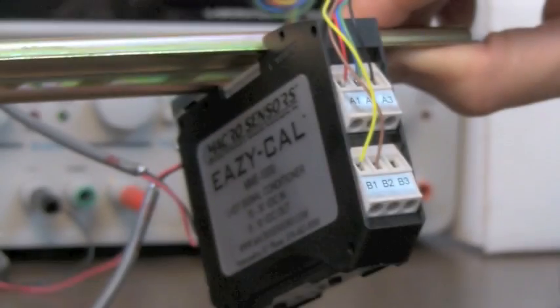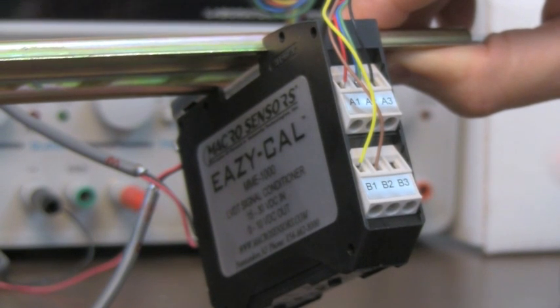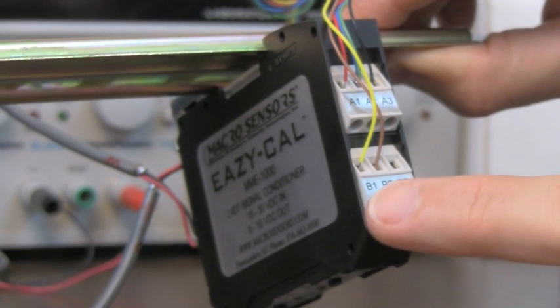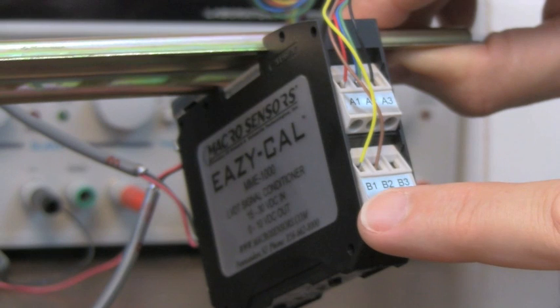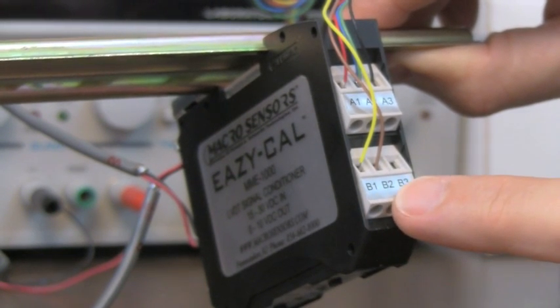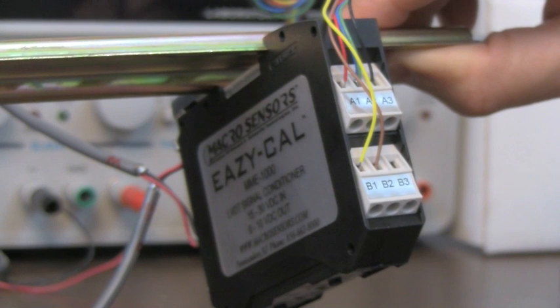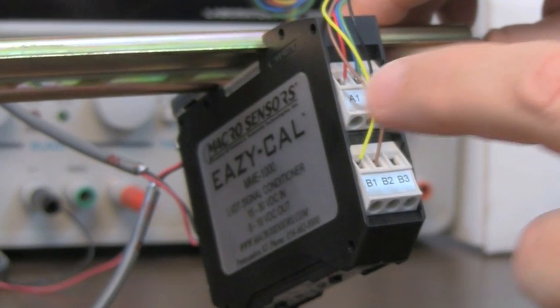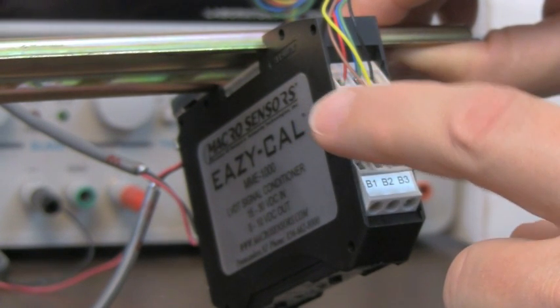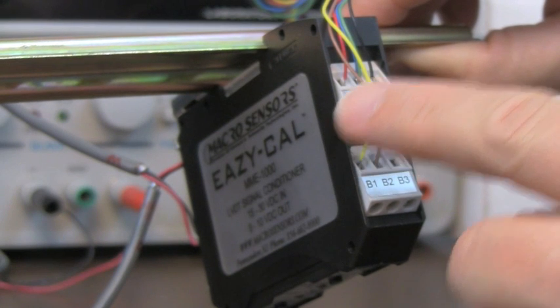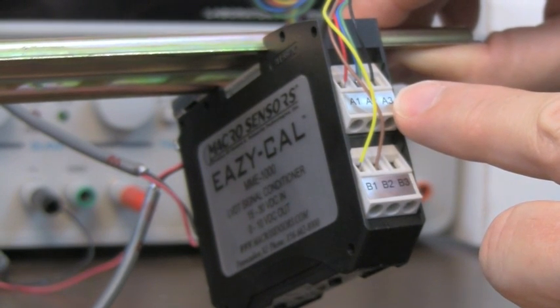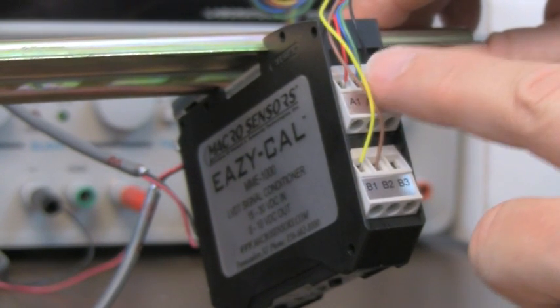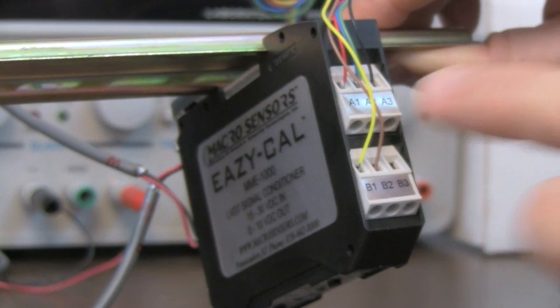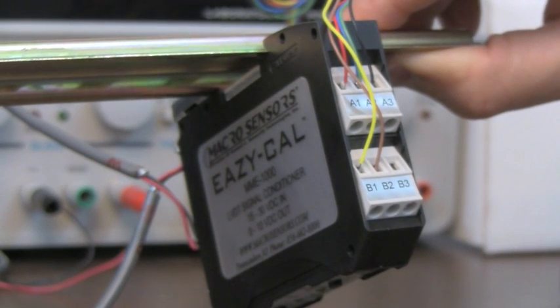The LVDT is connected to the top set of terminals on the EAZY-CAL. The two primary wires are connected to terminals B1 and B2, with yellow connected to B1 and brown connected to B2. The secondary wires connect to terminals A1, A2, and A3, with red connected to A1, black connected to A3, and both blue and green, which are the center tap wires, connecting to A2.